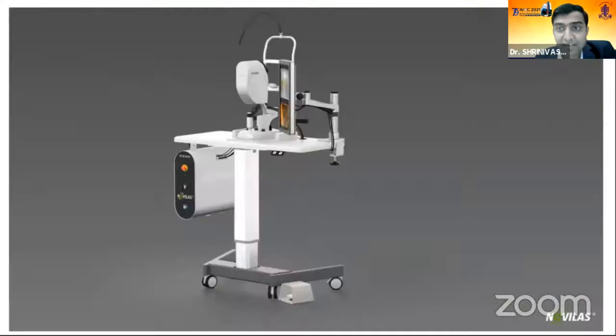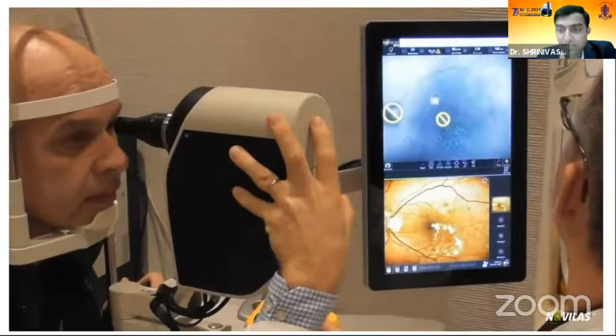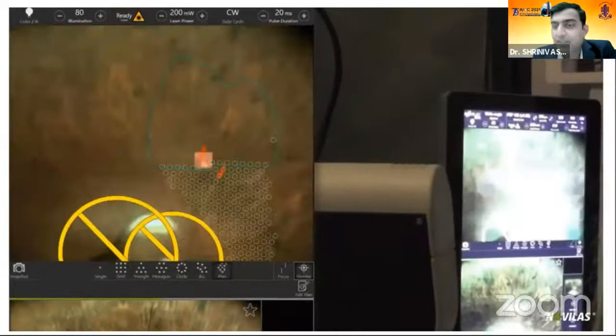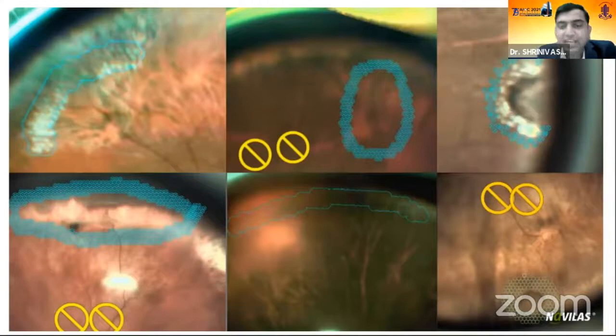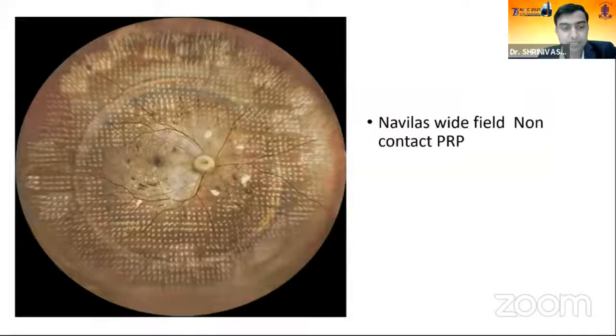The navigated laser, NAVILAS, makes treatment very easy. You obtain the angiographic photo, mark the areas you want to treat, and it has an excellent eye-tracking system — even if the eyelid closes, it doesn't fire. It has come into non-contact PRP as well. It hits the marked lesions automatically, making life easier for vitreoretinal surgeons. We also have Navilas wide-field non-contact PRP available.